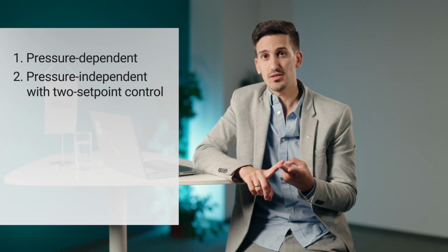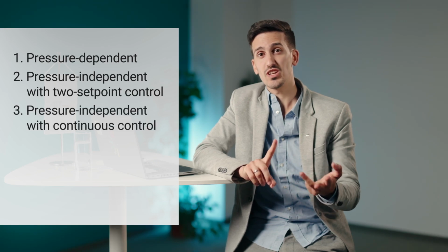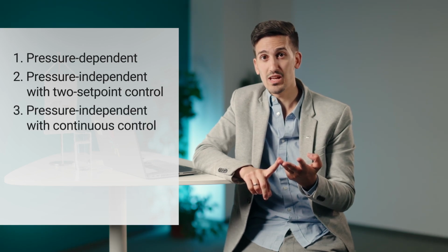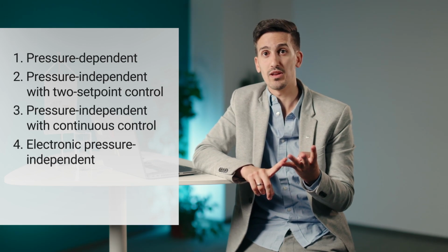In our simulation, we tested the following hydraulic variants: pressure-dependent, pressure-independent with 2 set-point control, pressure-independent with continuous control, and electronic pressure-independent. In each variant, we measured the energy consumption of the pumps, trying to find out which variant can save the most energy.